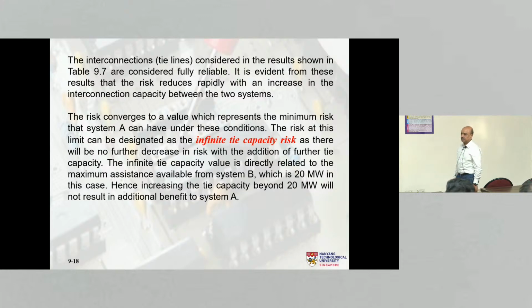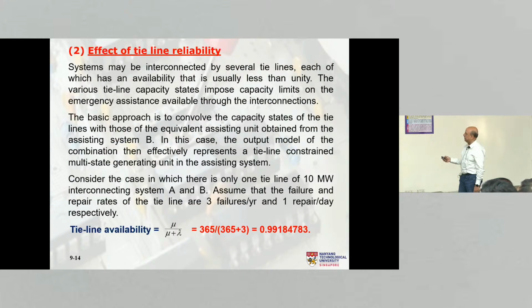Infinite tie capacity risk. That means regardless of how much you increase the capacity of the tie line, it's not going to increase any further, as there will be no further decrease in risk with the addition of further tie capacity. So it's called infinite tie capacity risk. The infinite tie capacity value is directly related to the maximum assistance available from system B, which in our case is 20 megawatt. Hence, increasing the tie capacity beyond 20 will have no benefit to system A.